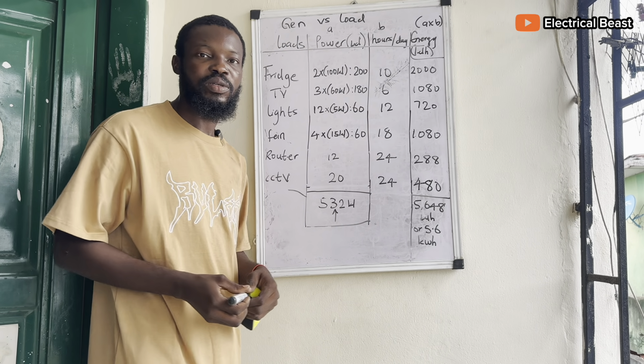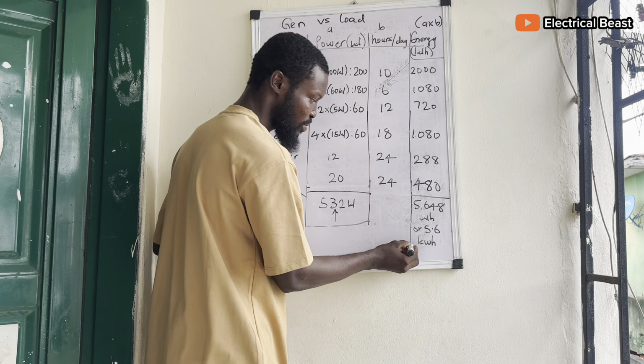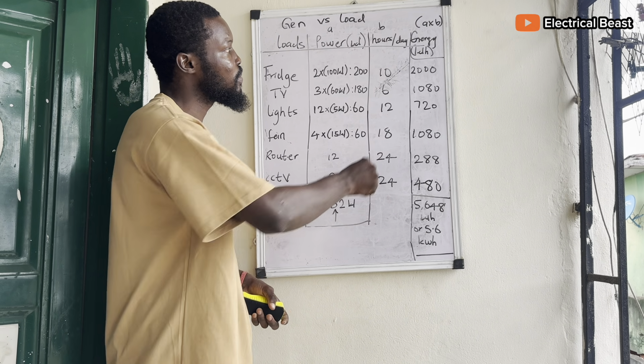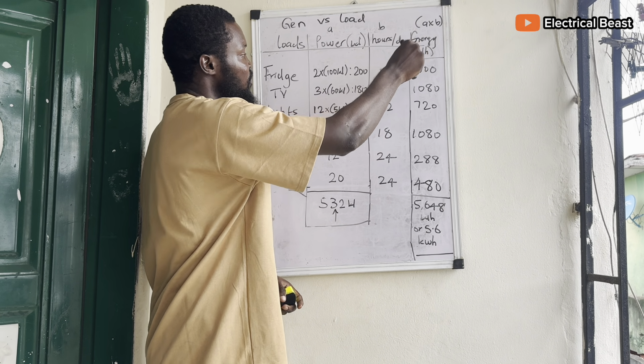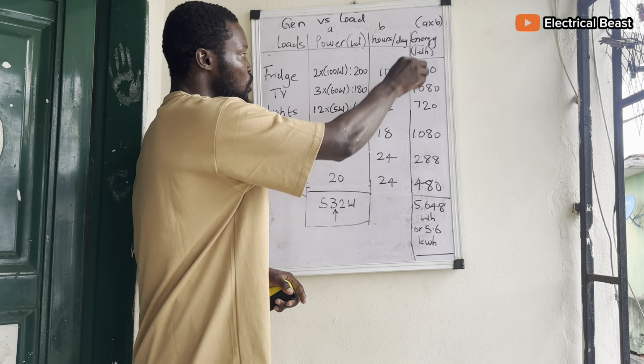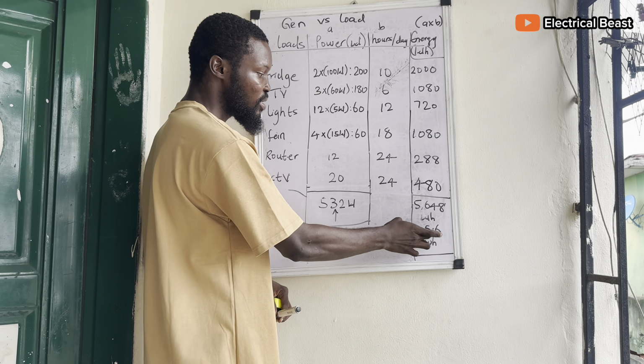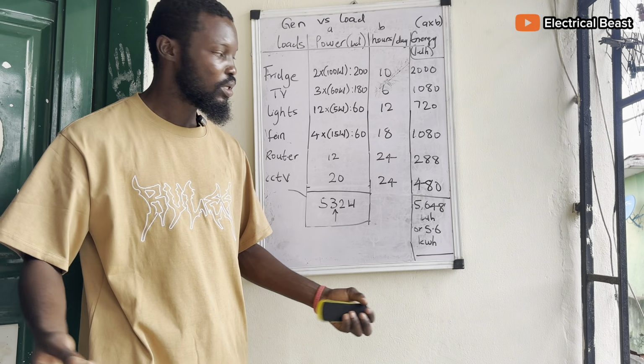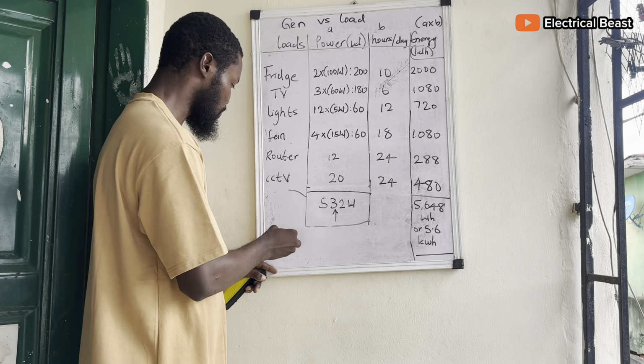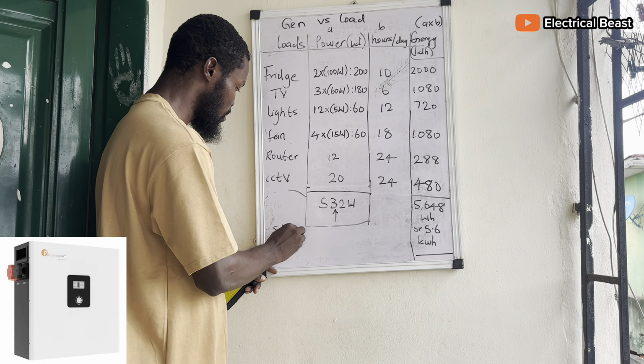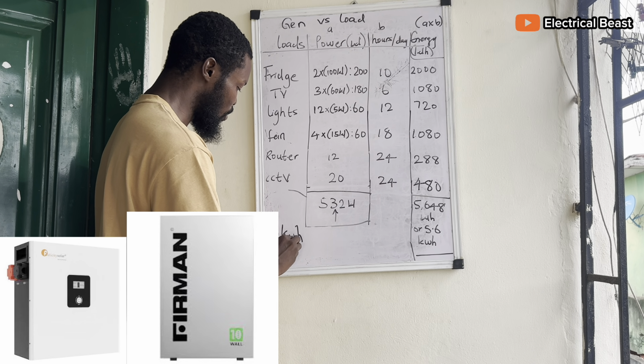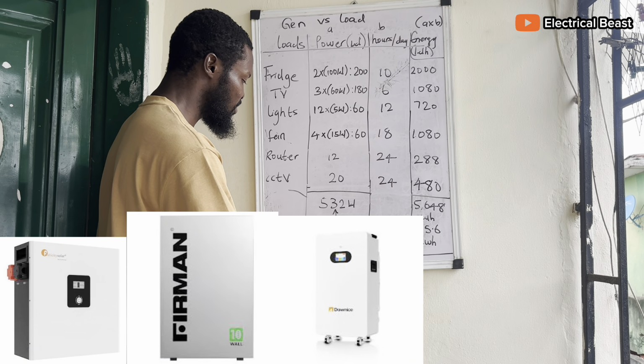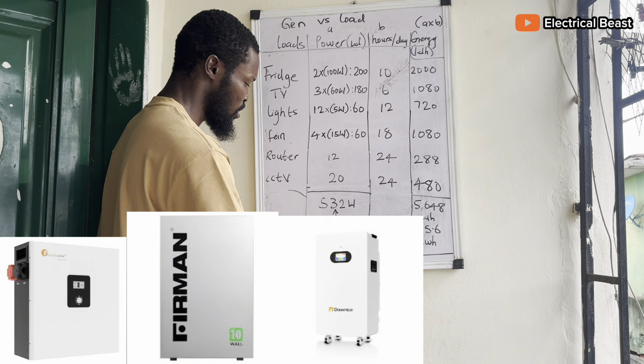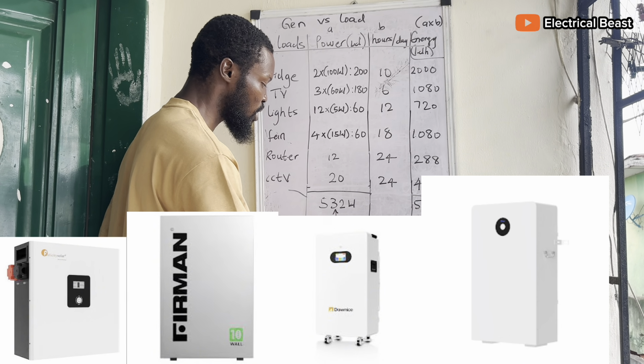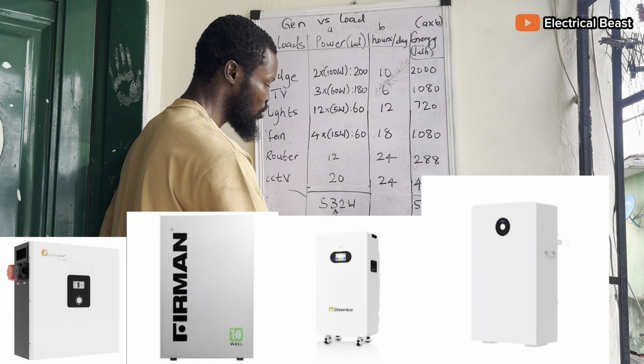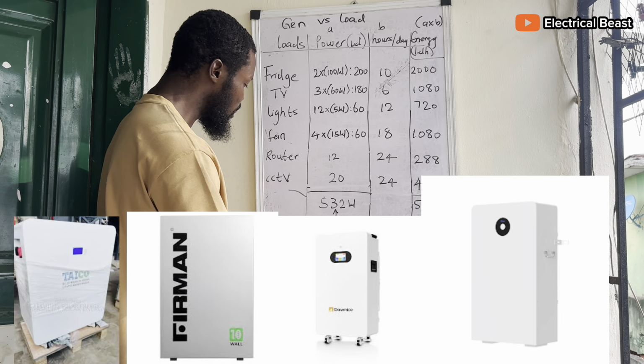Okay, then for your battery, now you're talking about a lithium battery here. Look at this column. You see that the total amount of energy per day on this column adds up to 5.6 kilowatt hour. It's very simple. Now, lithium batteries come in kilowatt hour. We have 5 kilowatt hour, 10 kilowatt hour, 15 kilowatt hour. Some brands have 16 kilowatt hour, 16 kWh. Then we have 20 kilowatt hour.